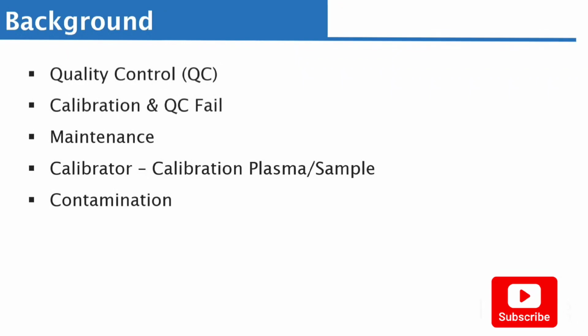So what maintenance does is to kind of do a background check. It will do some flushes of these very channels. It washes off the channel, flushes the channel to make sure there's no blockage, maybe like a clot or cell growth or cell multiplication in a channel, or it could even be bacterial contamination in that channel. So it will flush it and then do the background check. Once it has flushed it and done the background check, if the background check and everything come out okay, then the maintenance has passed. But if it detects any problem during the process, the maintenance will fail. So the same way you manage your samples, the same way you manage the analyzer when you are running the patient sample, in the same way you also manage it when you do maintenance.